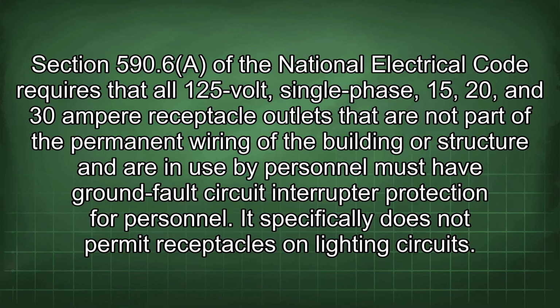Section 590.6 of the National Electrical Code requires that all 125-volt single-phase, 15, 20, and 30 ampere receptacle outlets that are not part of the permanent wiring of the building or structure and are in use by personnel must have ground fault circuit interrupter protection for personnel. It specifically does not permit receptacles on lighting circuits.